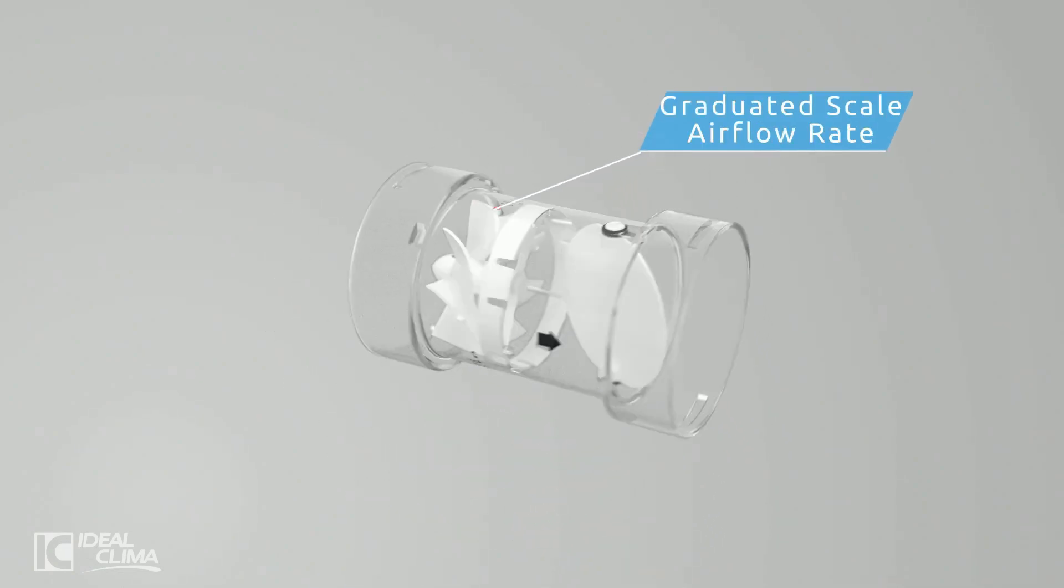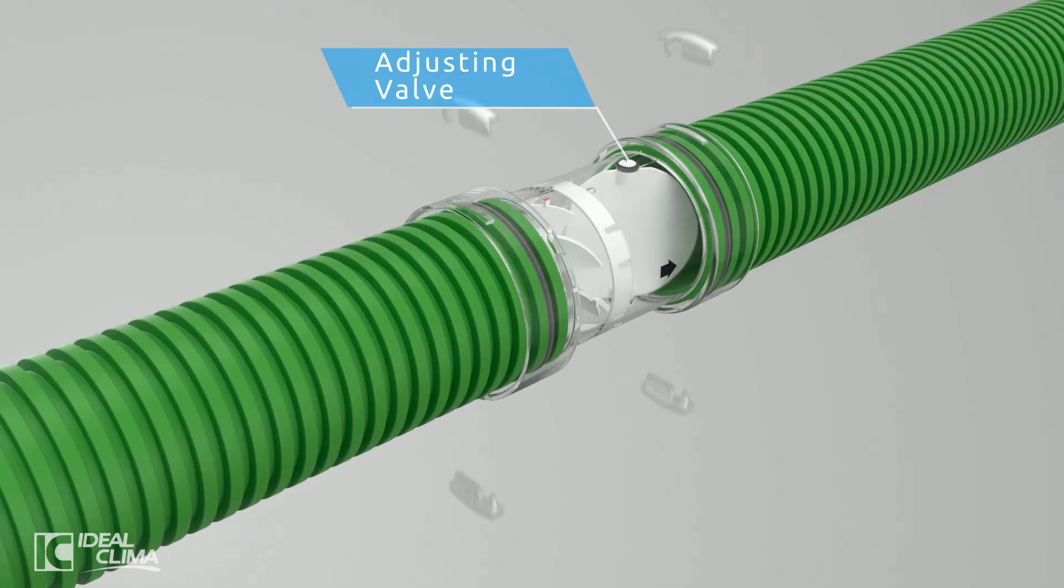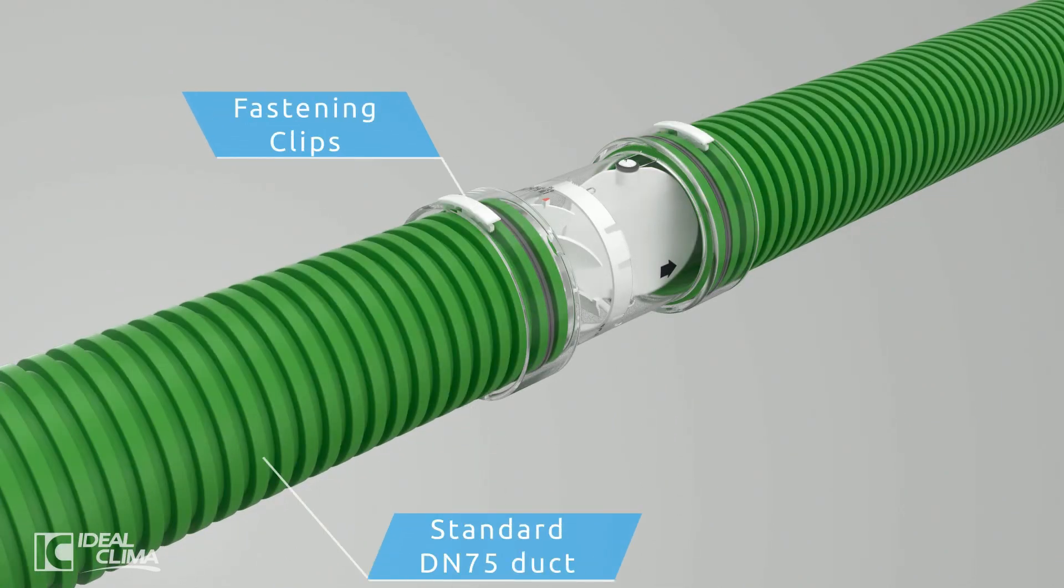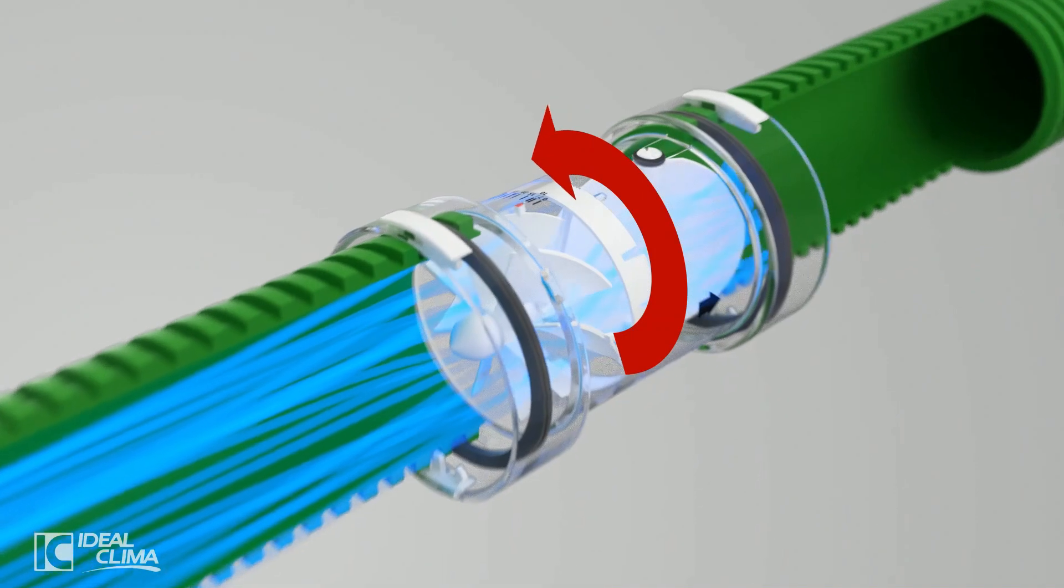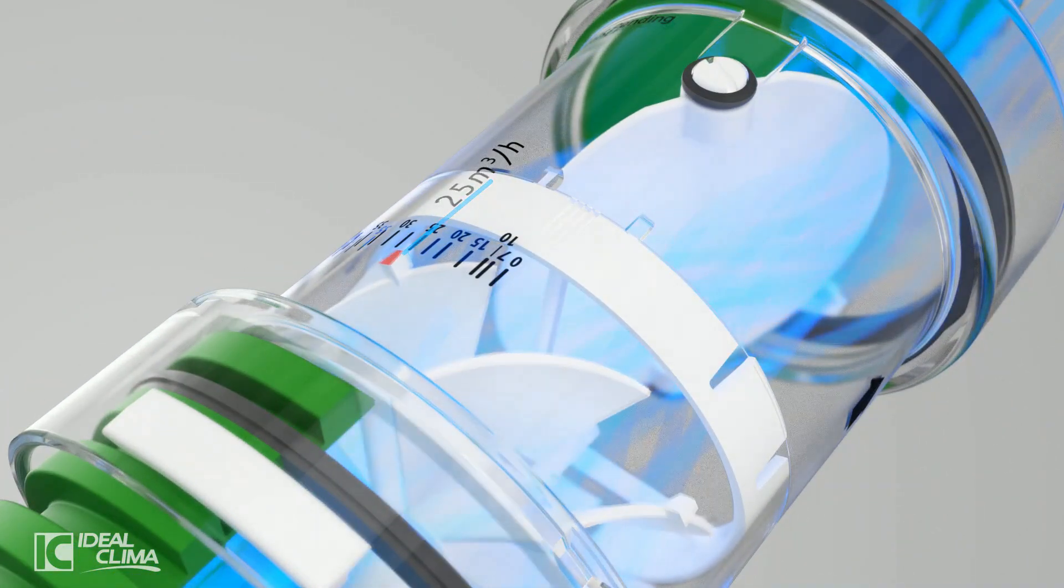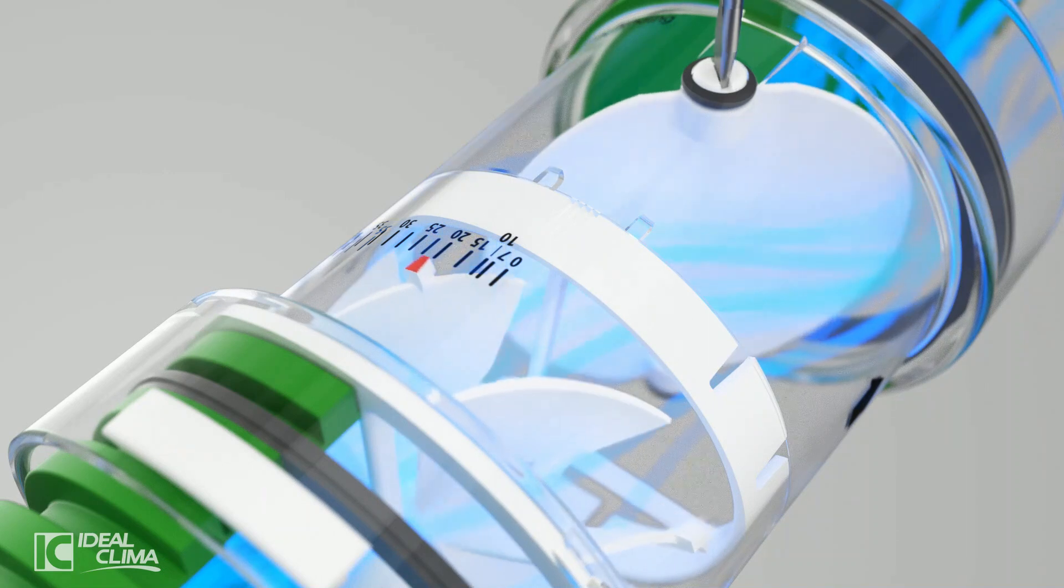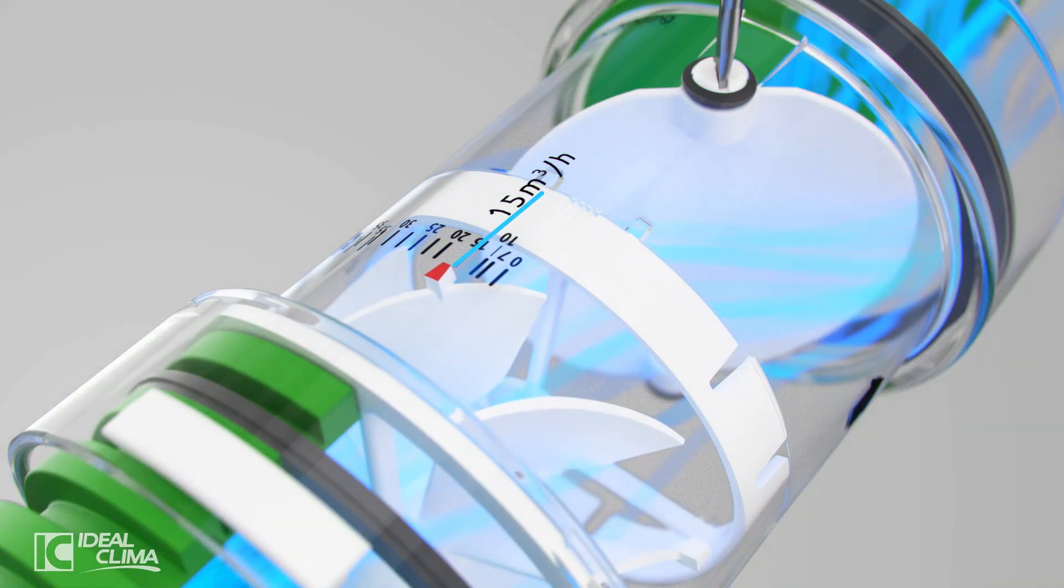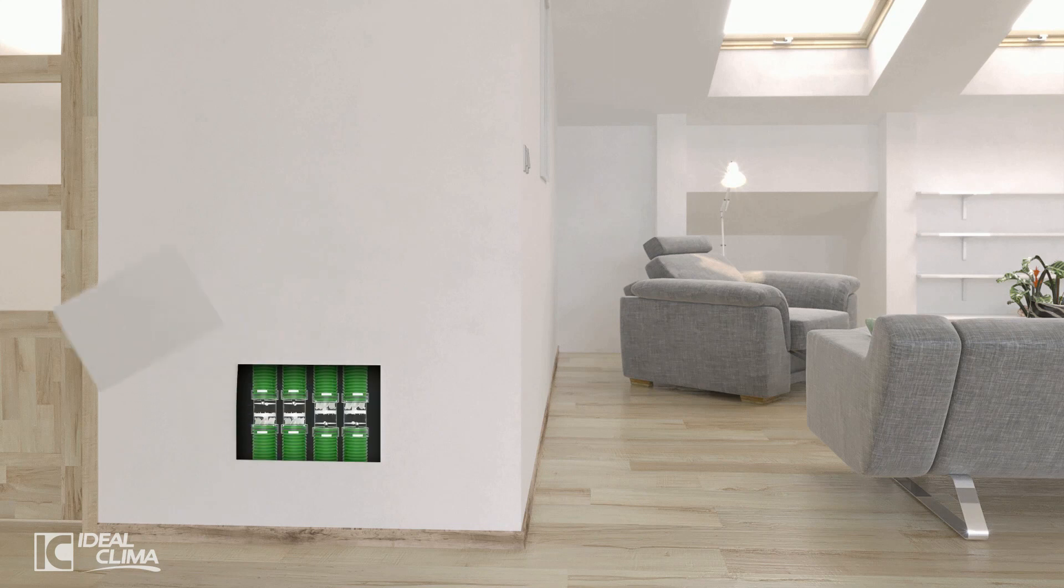MetroVent features a graduated scale and an adjustment butterfly valve. The fastening clips allow for secure and quick installation of MetroVent along the DN75 duct. The airflow moves the hand of the turbine along the scale, the displacement is proportional to the airflow in the duct, allowing a quick and clear reading. By rotating the embedded butterfly valve, the airflow can be quickly adjusted.